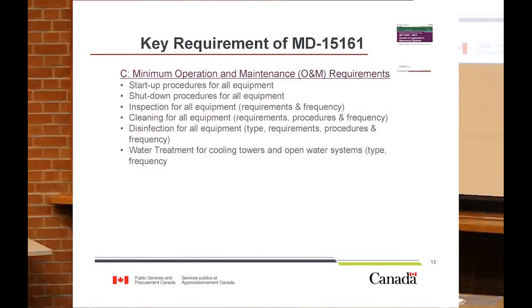The next key requirement is minimum operation and maintenance requirements for the various systems: requirements for startup of equipment, shutdown of equipment, and inspections of equipment, with minimum frequencies and requirements. Cleaning of equipment, again with minimum requirements, frequencies, and procedures. Disinfection of equipment, as well as water treatment requirements for cooling towers and open water systems.